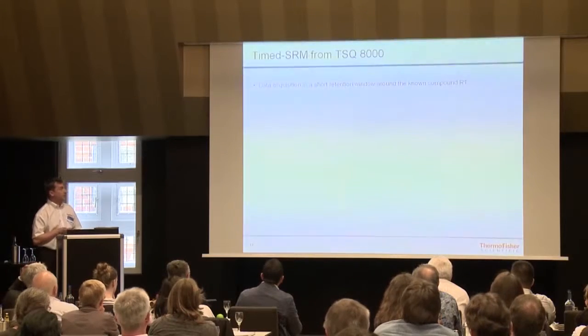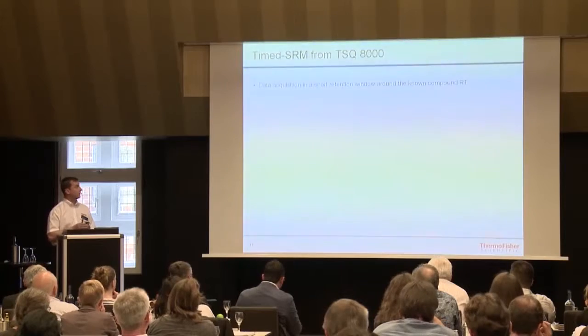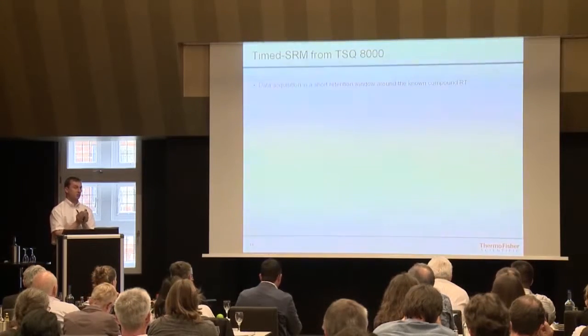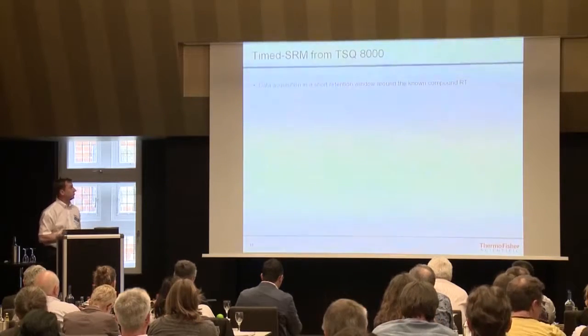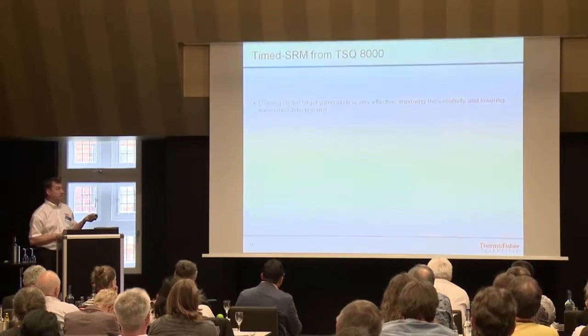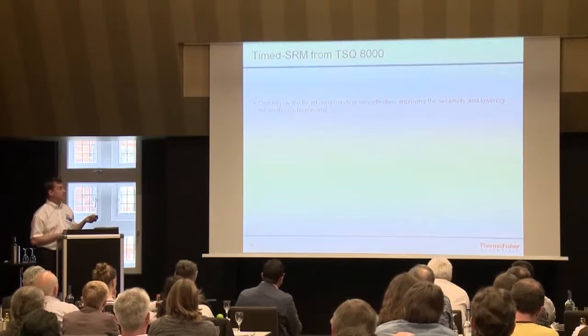We also used the acquisition mode called timed SRM. The timed SRM acquires data based on the known retention time of each compound, allowing you to optimize the duty cycle of your instrument so that you don't waste any time. You're just focusing on the targets, and because the dwell time is really effective, you can improve the sensitivity and lower your detection limits.